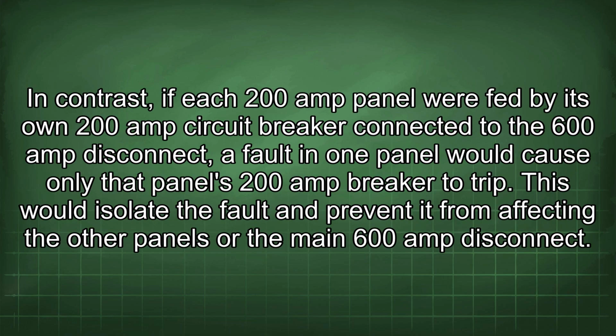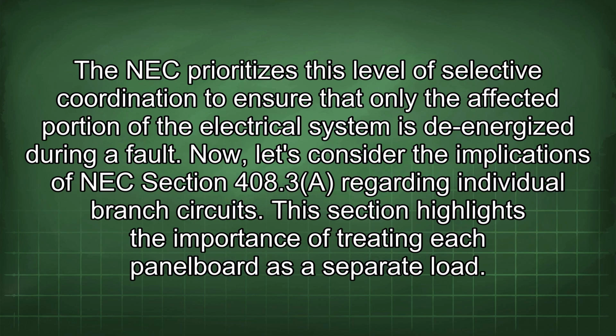In contrast, if each 200 amp panel were fed by its own 200 amp circuit breaker connected to the 600 amp disconnect, a fault in one panel would cause only that panel's 200 amp breaker to trip. This would isolate the fault and prevent it from affecting the other panels or the main 600 amp disconnect. The NEC prioritizes this level of selective coordination to ensure that only the affected portion of the electrical system is de-energized during a fault. Now, let's consider the implications of NEC Section 408.3 regarding individual branch circuits.